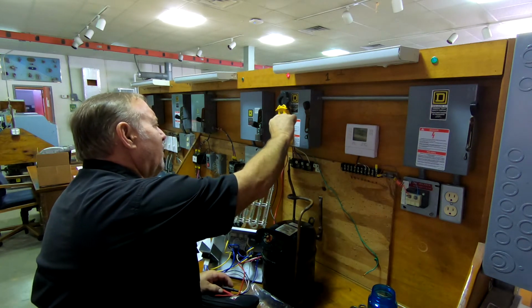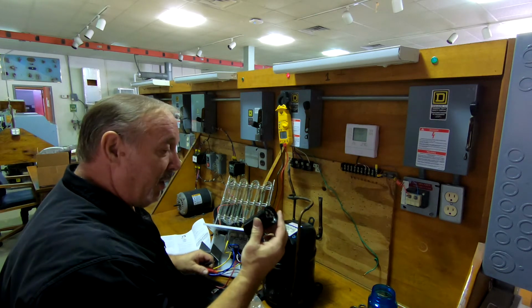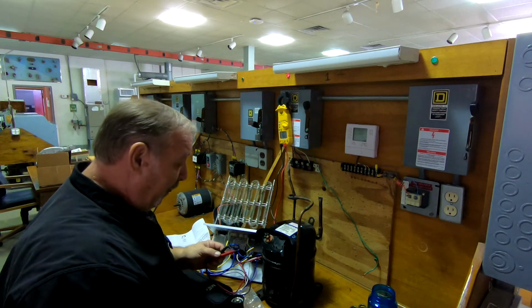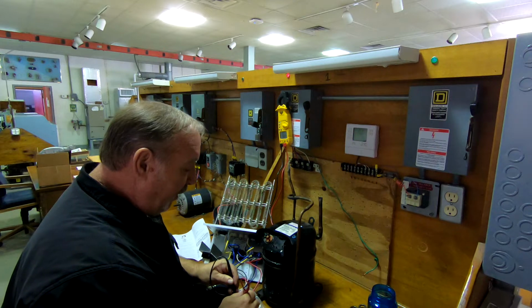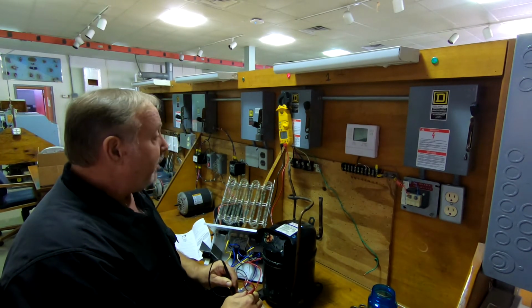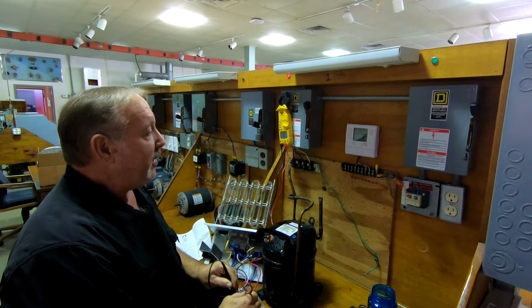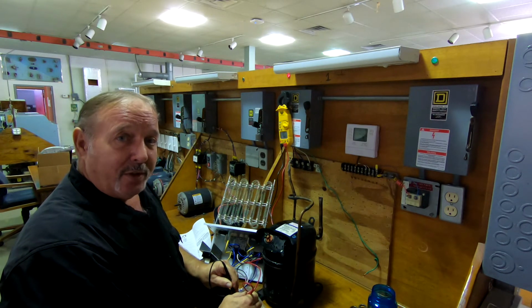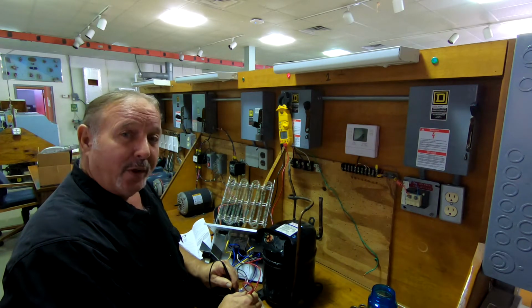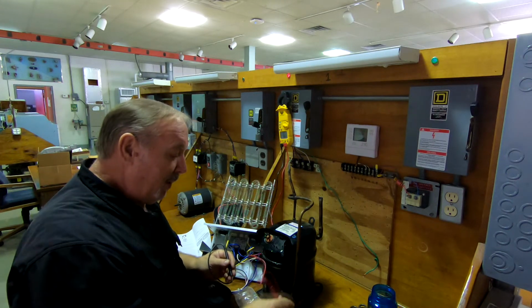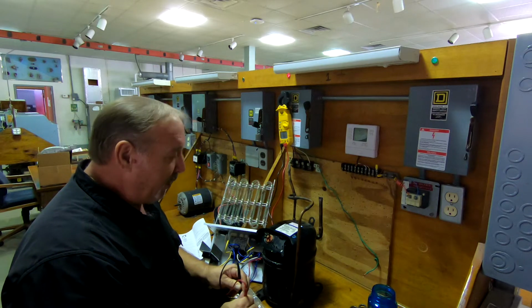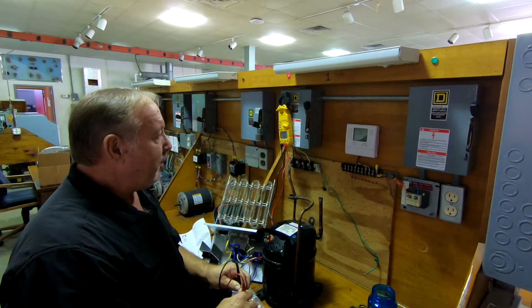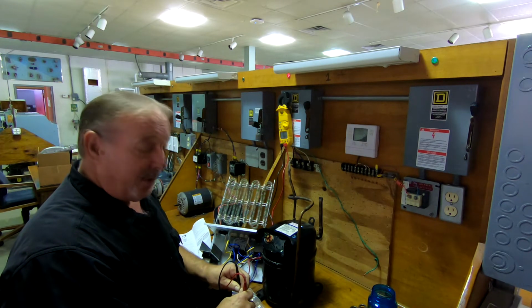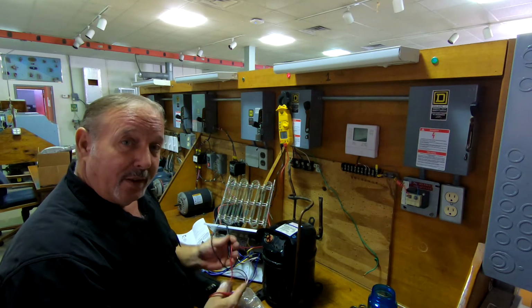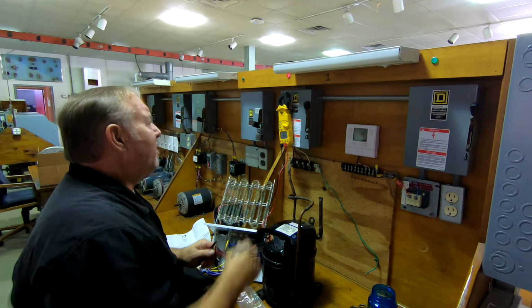All right. So the next reading up the scale is microfarads. So I have a start capacitor, I have a run capacitor. So I'm going to measure the microfarad or the capacitance, and it's going to take a moment. As you can see, there's dotted lines across the bottom display. That's because the battery is charging the capacitor, and now it's showing me it's 156.6 microfarads. If I take the same set of circumstances and I want to measure the run capacitor, it's going to take a few moments to charge up. And now we have a value, 12.67 microfarads, which matches what the label on the front tells me. All right, moving right along.